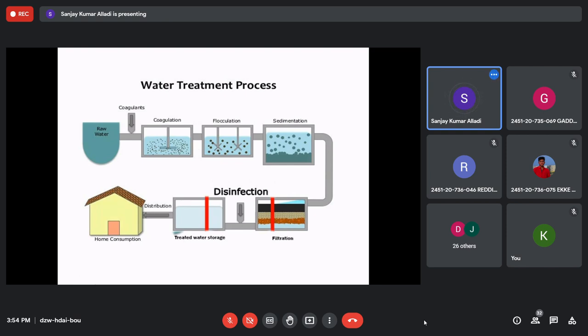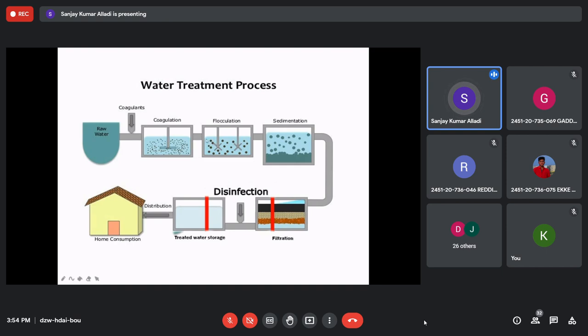The dust particles adhere to coagulant molecules — this is called a floc. First, we add the coagulant and disperse its molecules throughout the liquid tank; this is called coagulation. Once the coagulant molecules are dispersed in the water, they collide with dust particles and frequent collisions cause adheration. That process is called floc formation or flocculation.